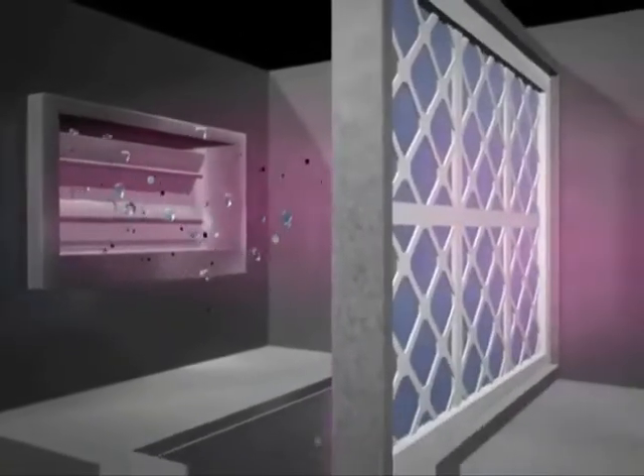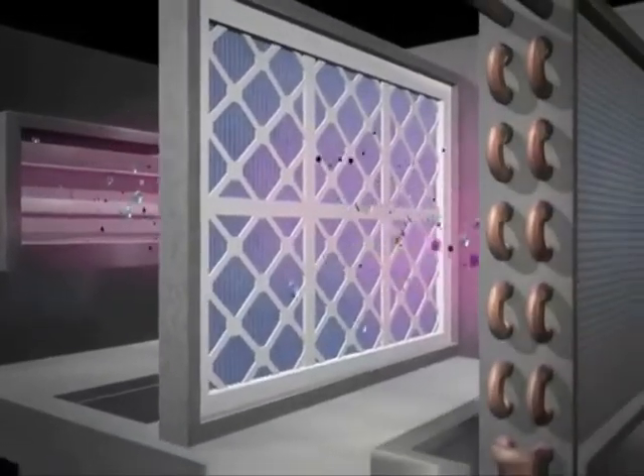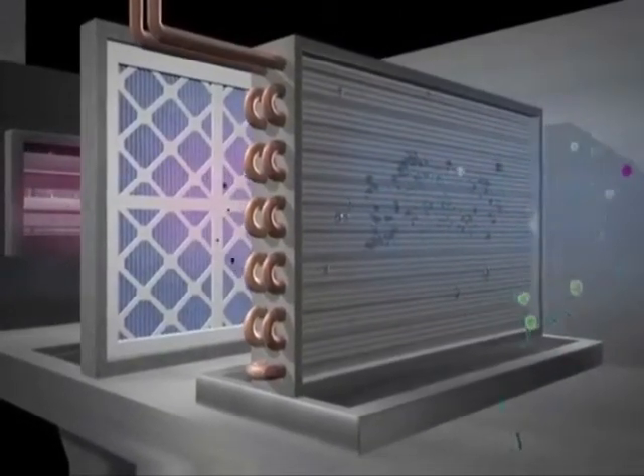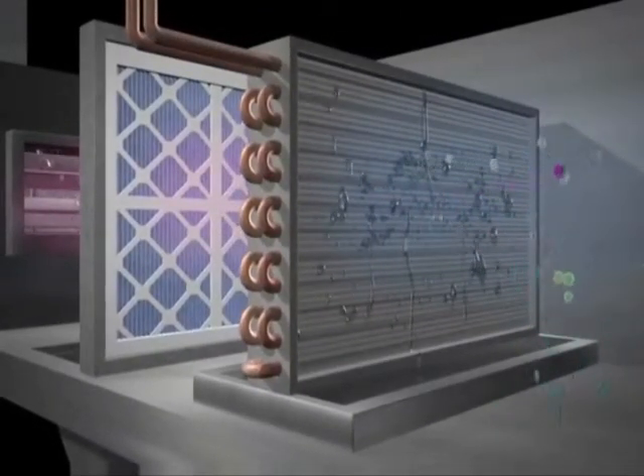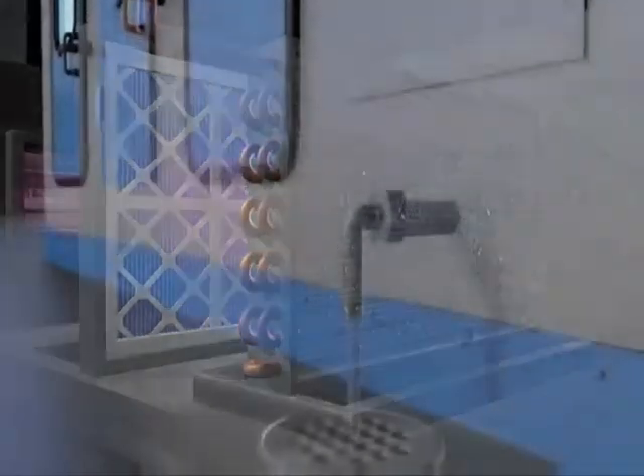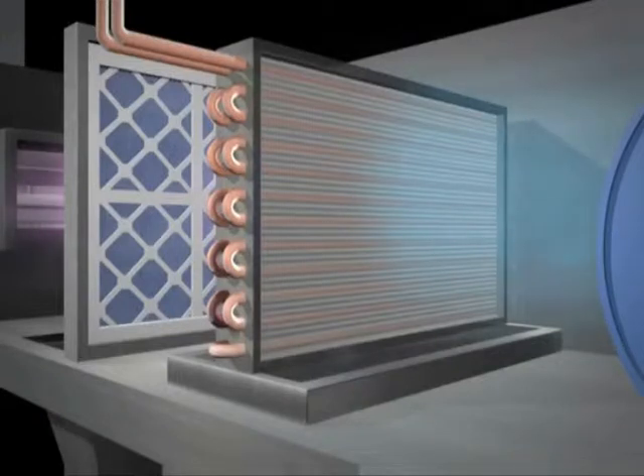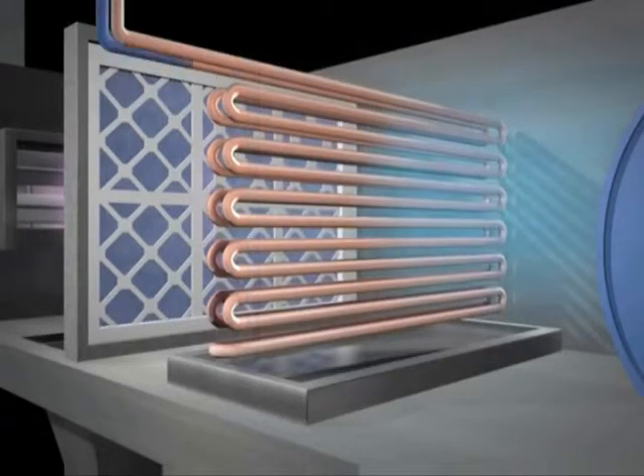From the people in the building, a percentage of fresh air is then added. This mixed air is passed through the primary filters to remove big dirt particulates. The resulting condensate in the cooling coil is drained away to the sewer. The heat from the building's air is absorbed through the coil fins by a cold liquid, typically chilled water, that is being pumped through the coil.